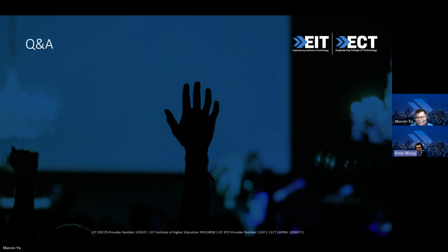Good question, Andrew. The answer is yes. The more utility have in terms of control over the network, the better. But depending on where you're located, distribution transformers generally have offload tap, so you can't change it unless you send somebody out to do it.